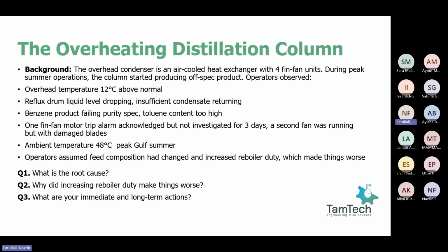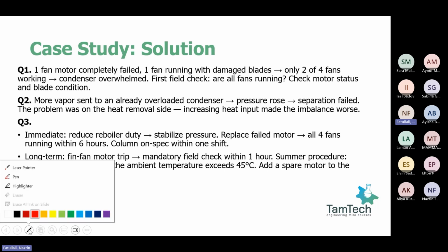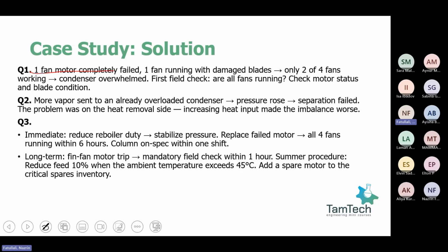What is the root cause? Firstly, someone walked out to the air cooler and found that one fan motor, let me use my pen, one fan motor had completely failed, completely dead.